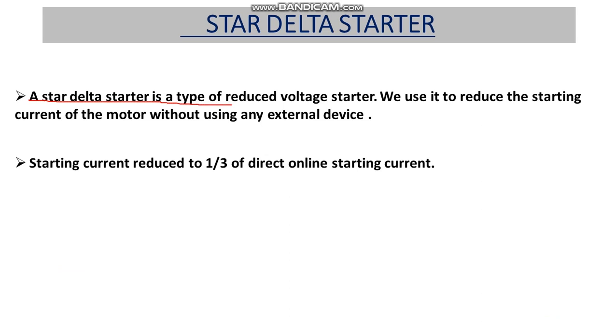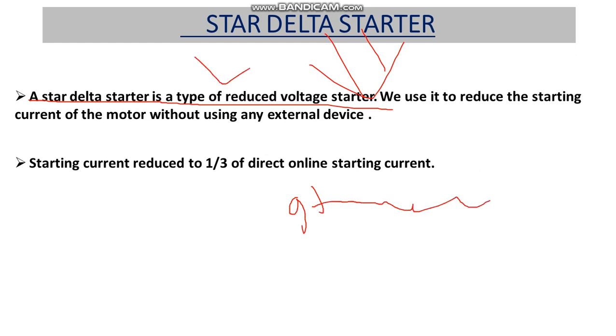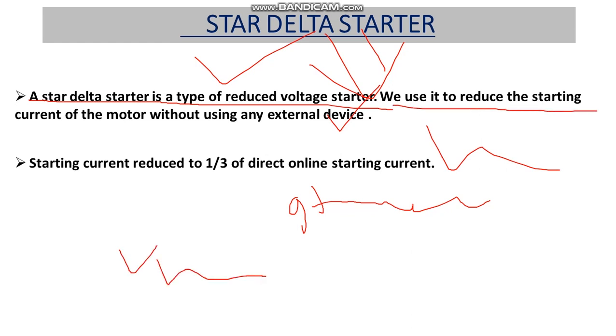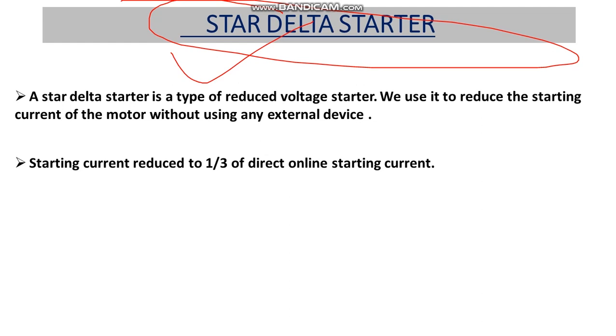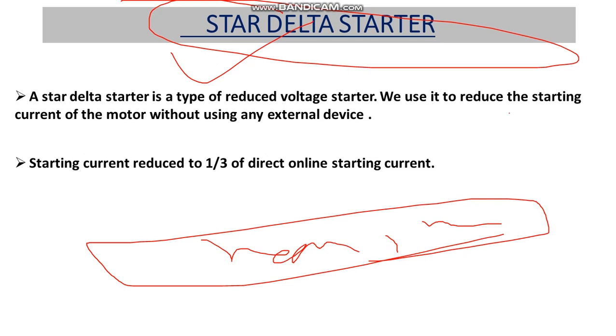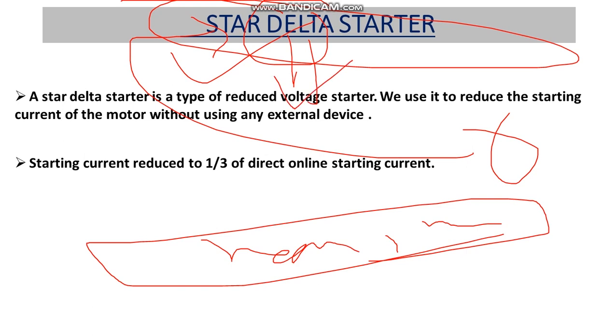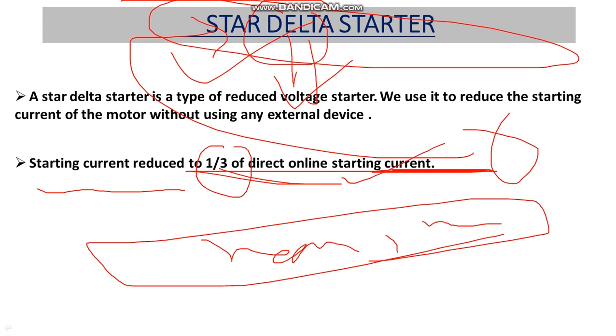That's why for higher-capacity motors we use a star delta starter. It is a type of reduced-voltage starter — it reduces the voltage in star condition, which reduces the initial current. This starter reduces the starting current to one-third of the direct-on-line starting current without any external device. Initially the motor operates in star connection, then converts to delta.